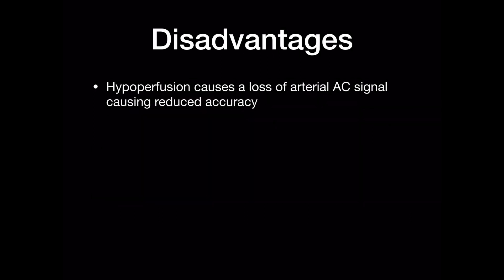If the patient is hypoperfused then this will cause a loss of the arterial alternating signal causing reduced accuracy. The probe can cause injury to patients with poor perfusion and burns have been reported in children.